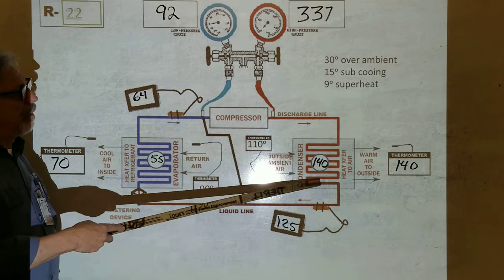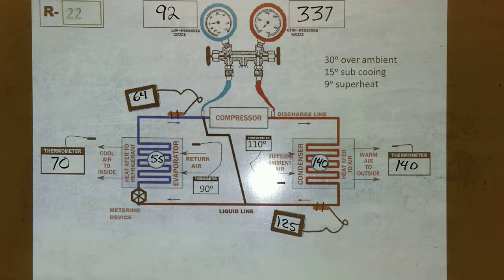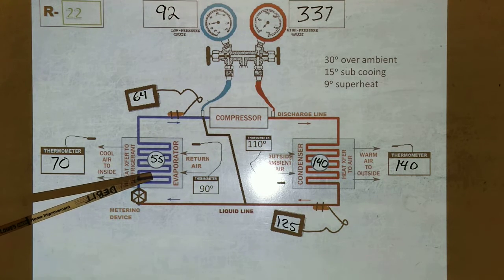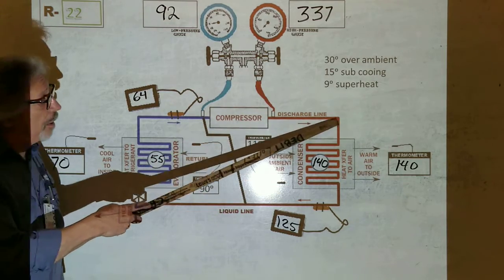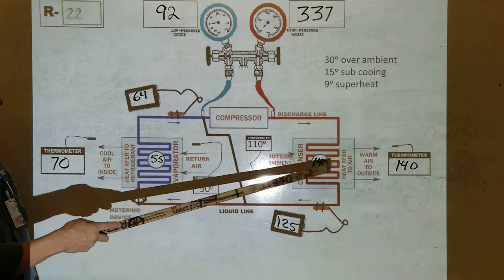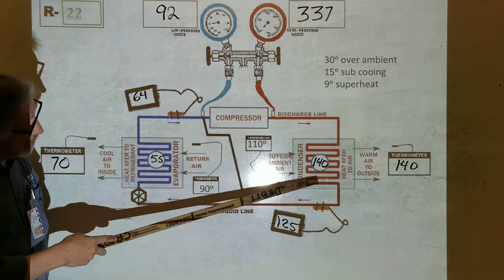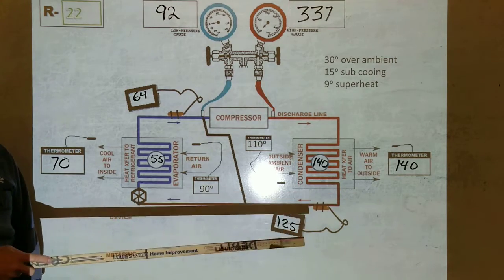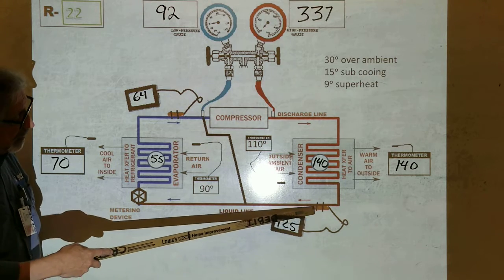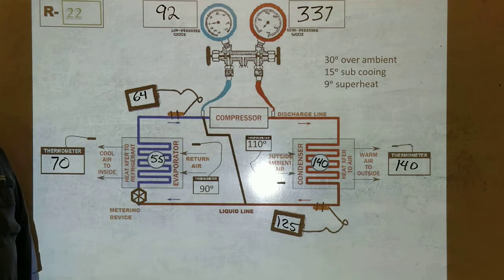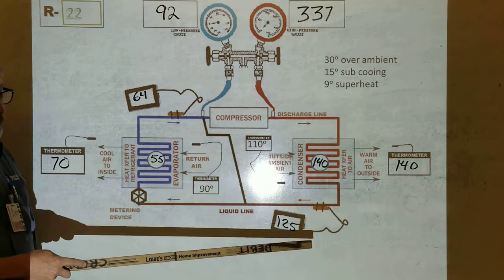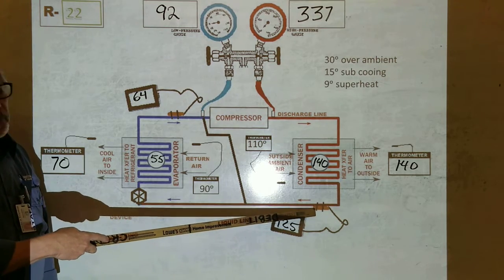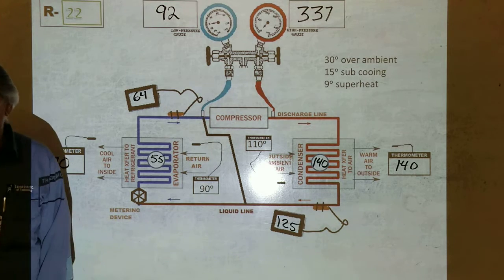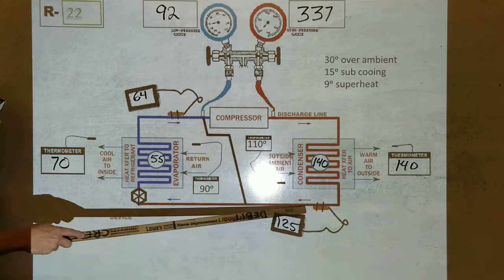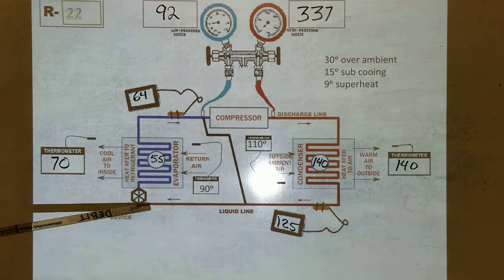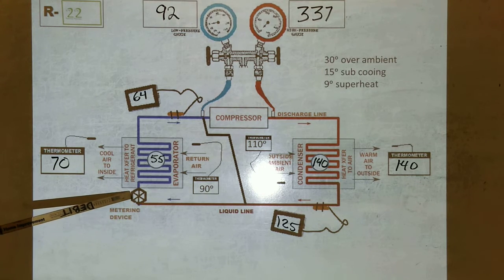Okay, so it's condensing, it's turning into a liquid. What did it do over here? It turned into a vapor, so over here, it's gonna turn into a liquid. So it's vapor going through here, it's gonna make that transition at that temperature and pressure until it comes out of that liquid line and cools off some more, meaning subcooling. So we can see the subcooling right here because our liquid line is no longer 140. Our liquid line has dropped below the saturation temperature to 125. See that? So that's making sure that there's only liquid in this line, because we need 100% liquid to go to the metering device. What happens at the metering device?